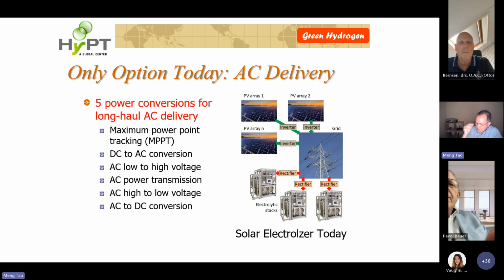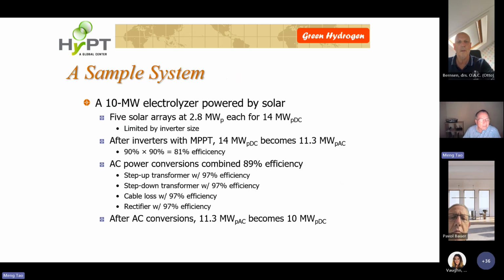And in Japan, they commissioned a 10 megawatt electrolyzer in about 2020. That's coupled through AC. So what we need to do is, on the solar side, we need to do maximum power point tracking. And then if it's a long haul power delivery, we need a step up transformer. First DC-AC conversion, then a step up transformer. And then once it reaches the electrolyzer, a step down transformer and a rectifier. So we can see how much energy loss there is in this case.